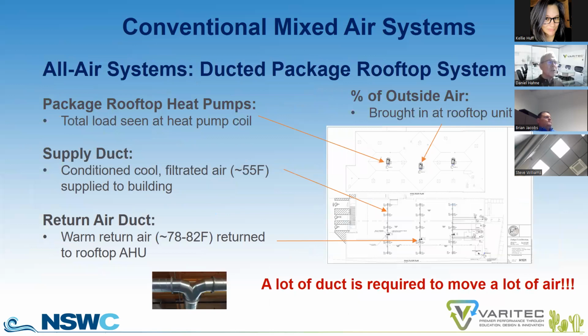Conventional systems use package rooftop units. We see them all the time. DX units, DX cooling, heat pump configurations, chill water air handlers for larger buildings. And we use these air handlers to supply 55-degree air approximately. We hope we get there with DX units in our environment, but we go to 55 so we can actually control the latent energy in the air, wring out some moisture so we can maintain humidity conditions within a building. Return air is then returned to these units and it's mixed with outside air at the air handler mixing section where it's conditioned at the coil and then resupplied to the space.